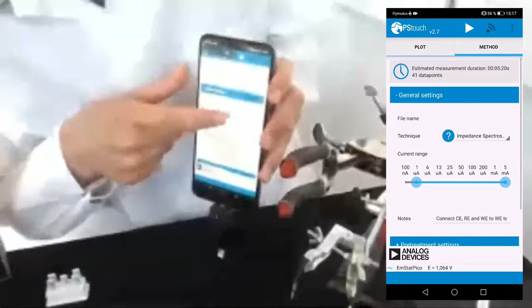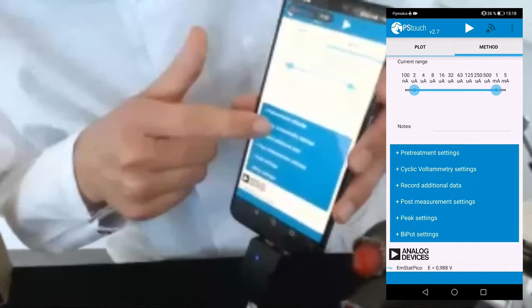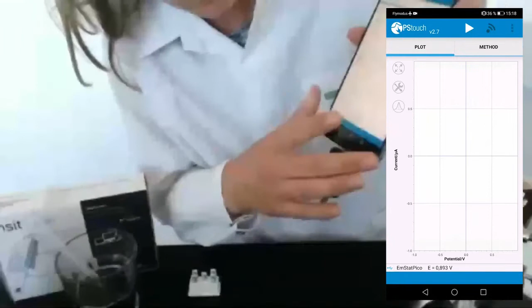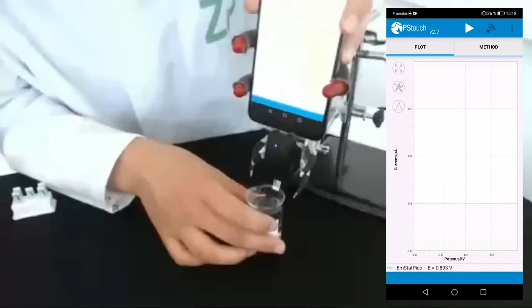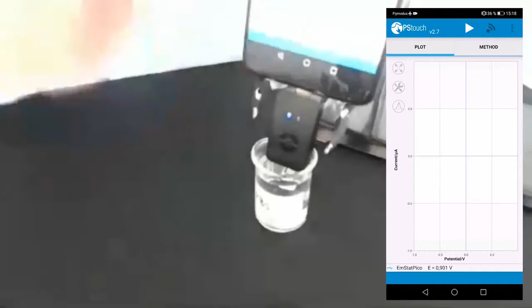But first, we need to change the method so that we have cyclic voltammetry, and we will set the parameters, like Lutz said, to 1 microamp to 1 milliamp, and then we will change the cyclic voltammetry settings. We will start with -0.1 volts, and then we will cycle up to 1.2 volts, and then we will go back down to -0.1 volts. Each step is 0.01, and our scan rate should be 0.1 volts per second. And then we will go to plot, and we will start the measurement. Be sure to cover all the electrodes with the solution, and then we will hit play.